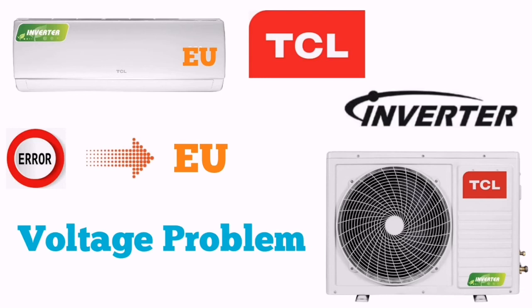And you have to check the connection if it is connected properly or not. And if it is connected properly, then restart again. If the fault remains unsolved after connecting again, please replace the outdoor power source board. If the fault remains unsolved after replacing the outdoor power source board, then you have to replace the intelligent power module board and your unit will be in working condition.